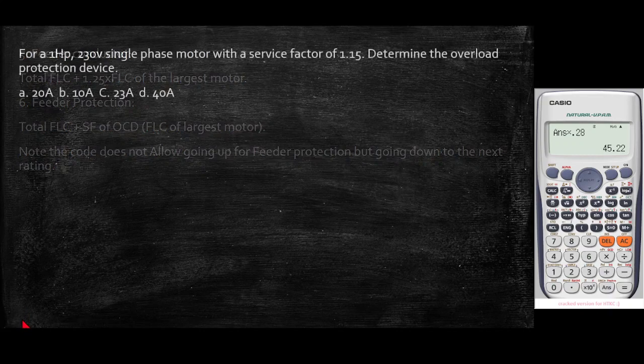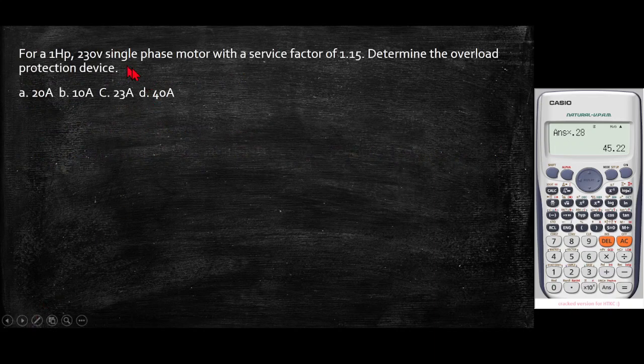Yan. Okay. So we have here a 1 horsepower, 230 volts single phase motor with a service factor of 1.15. So we need to determine the overload protection of the device. Yan. So kunin natin yung table.